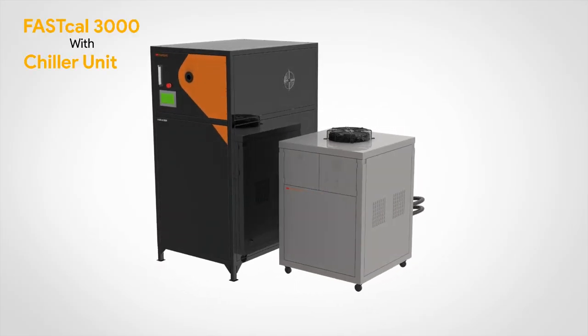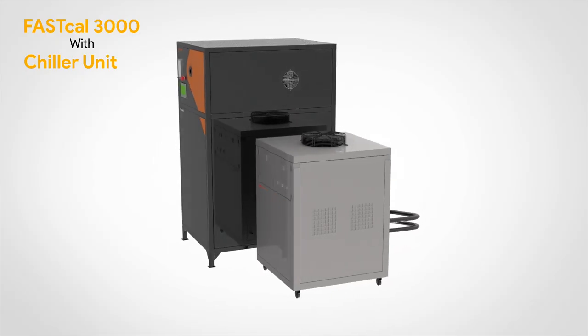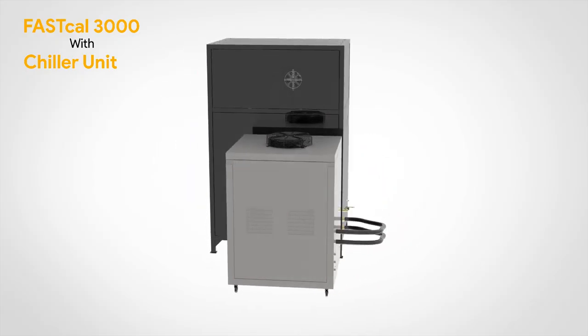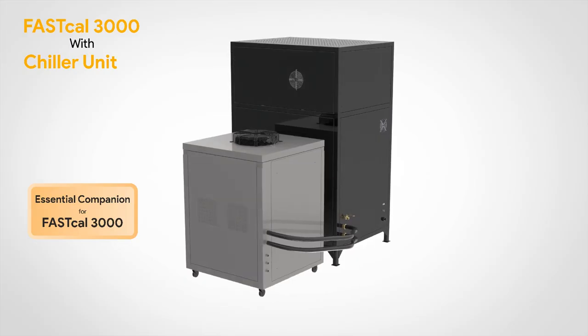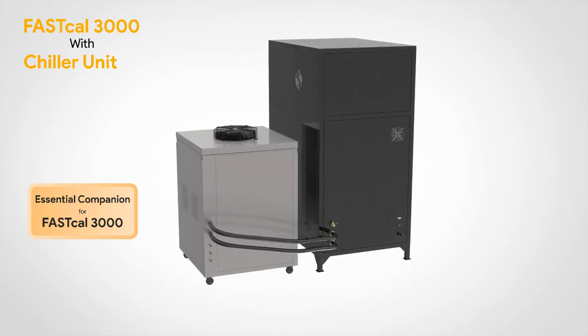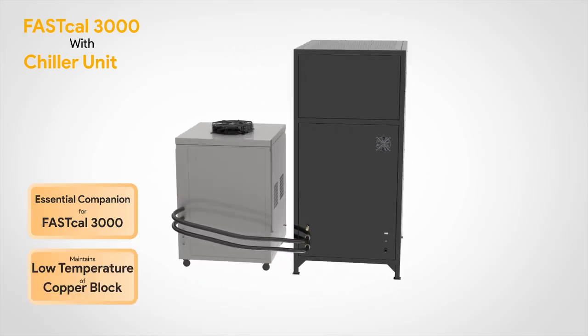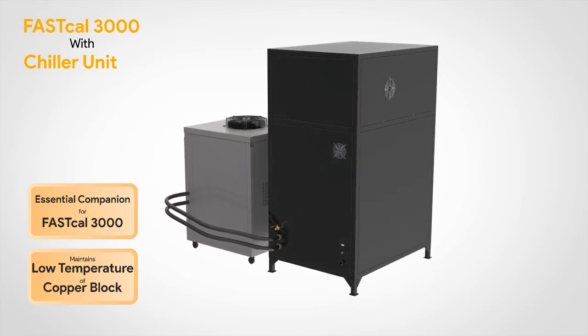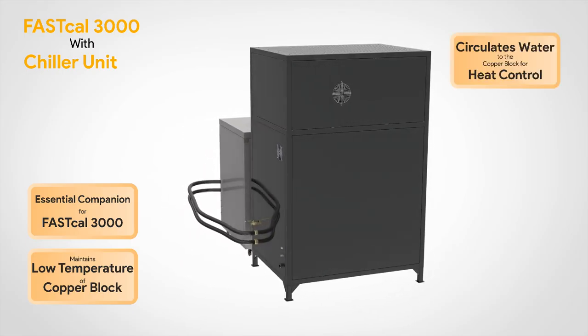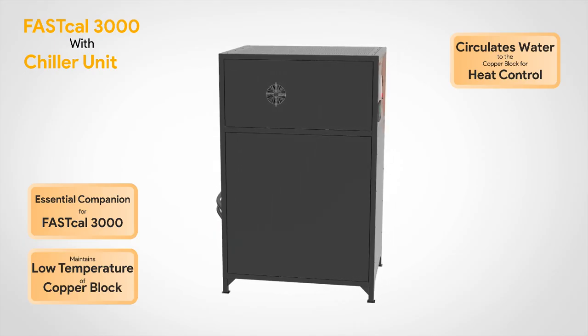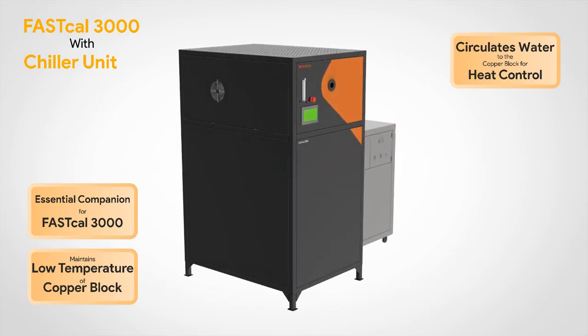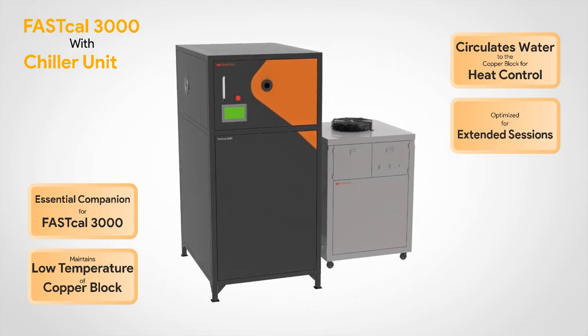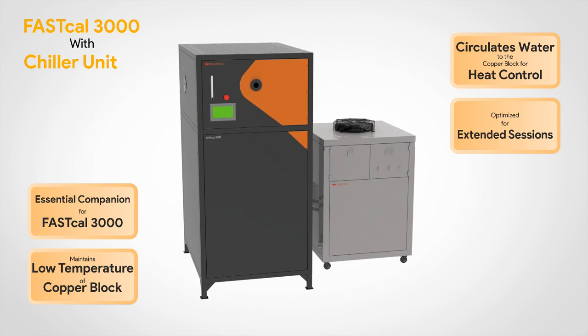This is FASTcal 3000 with chiller unit, an essential companion of the FASTcal 3000. The FASTcal 3000 comes equipped with this chiller to maintain stable, low temperature of copper block during calibration. The chiller circulates water through the copper blocks, absorbing excess heat and keeping their temperature low and stable. This ensures precise temperature control even during extended calibration sessions.